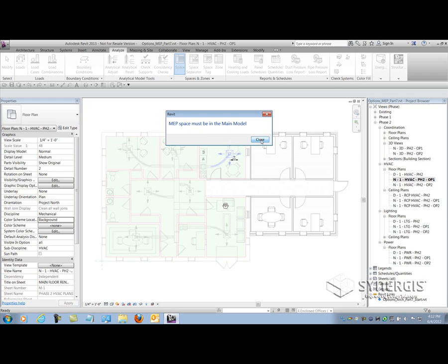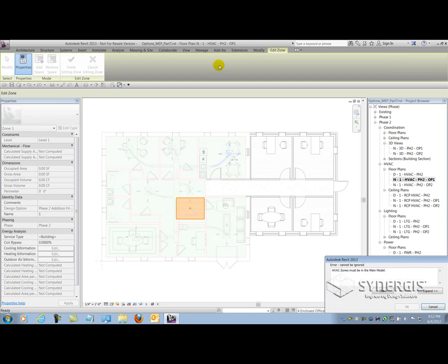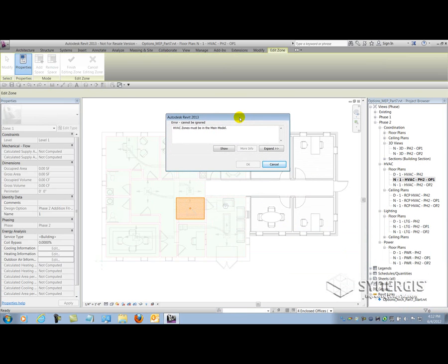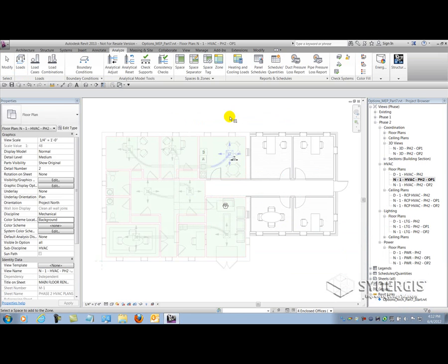I'm going to close that up and while I'm at it, might as well talk about zones too. When I click on zones, you'll see that I get exactly the same warning because zones have to use spaces. So zones cannot utilize design options either. Just be aware that when you get into your options inside your MEP systems that you cannot leverage design options. You're going to have to create separate files for each option.